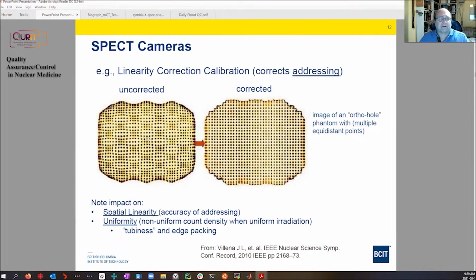So these are two intrinsic problems with SPECT camera detectors. And if these aren't corrected, these are big enough that if you tried to do SPECT on it where you reconstruct, you would have an image that would be unusable. The linearity correction essentially just recalculates where the address is. I'm not going to go into how. And this is what it looks like after the addressing with the linearity correction. So this calibration is very important. And if this calibration gets out of date in some way, if some of the parameters change, then this needs to be recalibrated. Otherwise, you run into these problems. So this has a big impact on spatial linearity and uniformity.